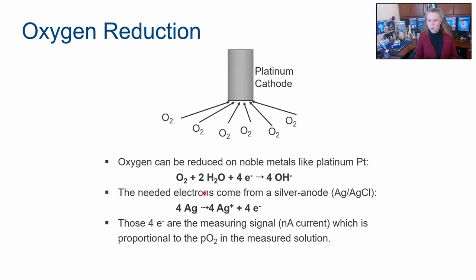So in an oxygen probe, in a polarographic probe, what happens is you have a platinum cathode and you have oxygen. And the oxygen is reduced on the platinum cathode. So oxygen gains electrons to make hydroxide. And that happens at the platinum electrode. And the electrons that they need come from the oxidation of silver. Silver loses electrons, becomes silver ions. This redox reaction causes a current to flow because we have electron flow, and electron flow is the definition of electricity. Okay.